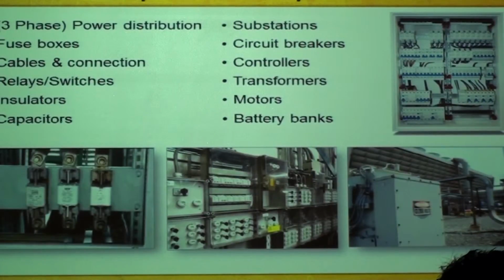Battery banks, again. If you have data centers, and I'm sure a lot of you are from data centers, battery banks are important, right? For a data center, that's the critical equipment. Like in an industry, a motor can be a critical equipment. In data centers, I think UPSs are critical, because if you lose data, boy, you're in big trouble, right? For a bank, they don't want to be losing the data, because then people like us will lose our money. So you want to make sure that you measure and inspect these components on a regular basis.